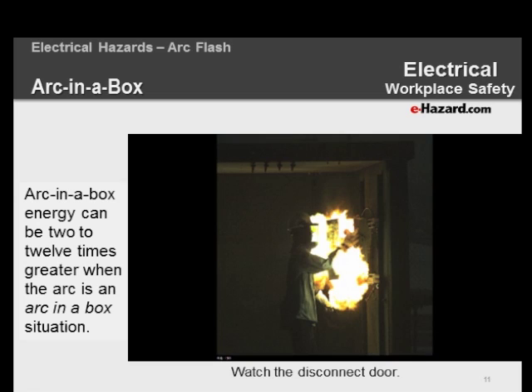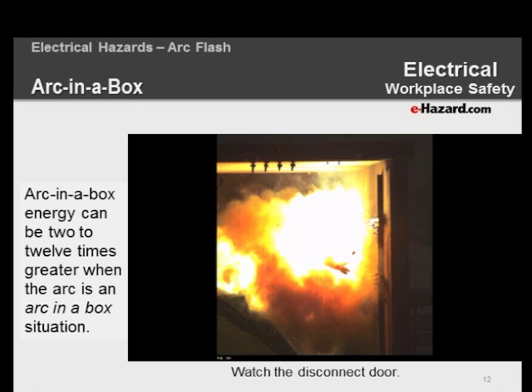Here you can see 1 cycle into the arc, a 60th of a second — the door is already halfway to the worker's face. By 6 cycles, the worker is completely gone, his body leaning back away from the door. We had cotton T-shirts on in several of these tests, and we never even ignited the cotton T-shirt, because the door basically hit the worker in the face and took him out of the way before the energy could really hit him.